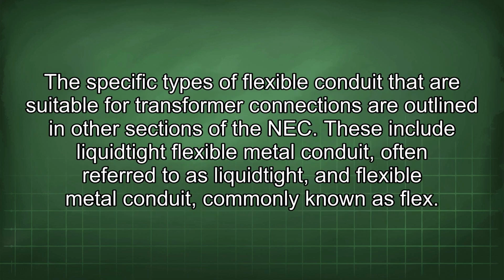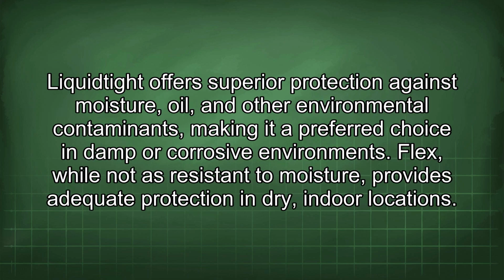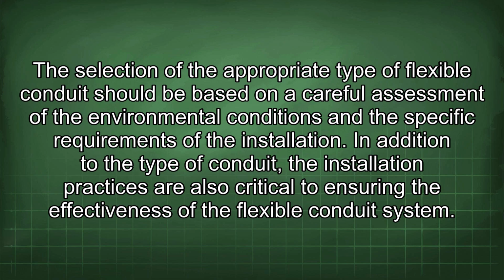The specific types of flexible conduit that are suitable for transformer connections are outlined in other sections of the NEC. These include liquid-tight flexible metal conduit, often referred to as liquid-tight, and flexible metal conduit, commonly known as flex. Liquid-tight offers superior protection against moisture, oil, and other environmental contaminants, making it a preferred choice in damp or corrosive environments. Flex, while not as resistant to moisture, provides adequate protection in dry, indoor locations. The selection of the appropriate type of flexible conduit should be based on a careful assessment of the environmental conditions and the specific requirements of the installation.